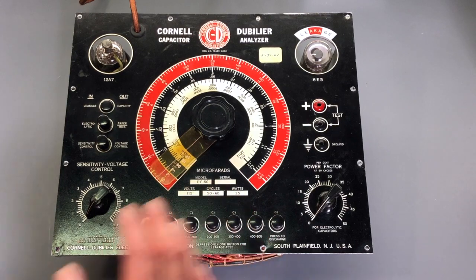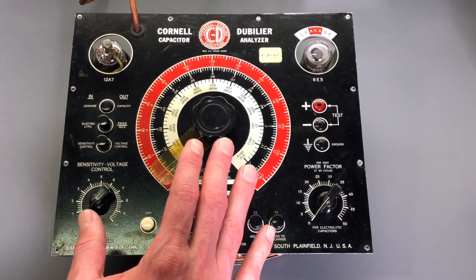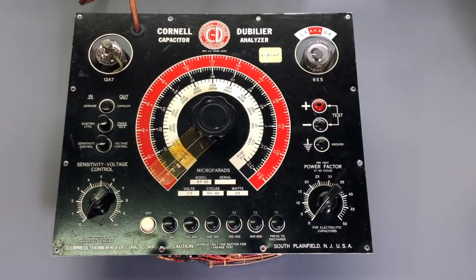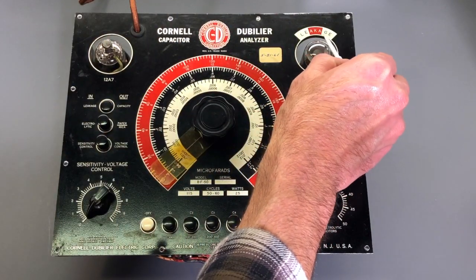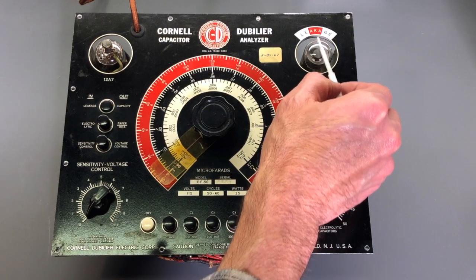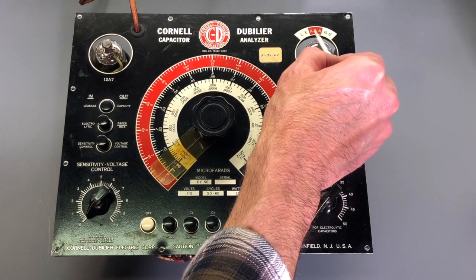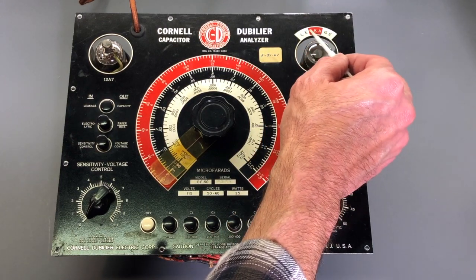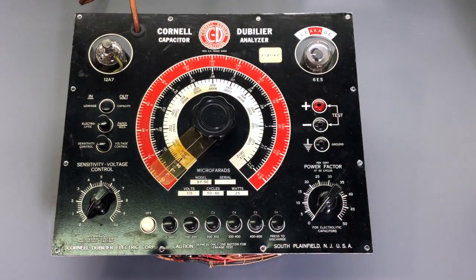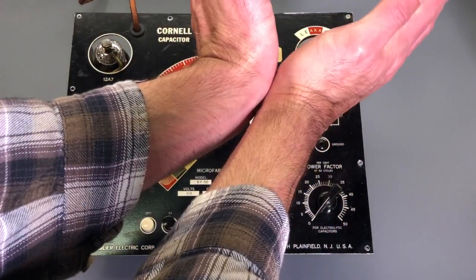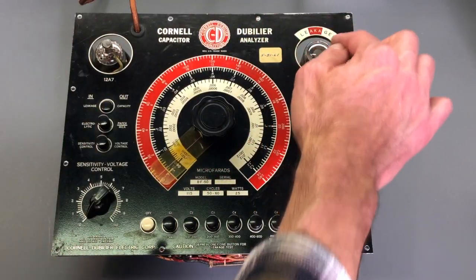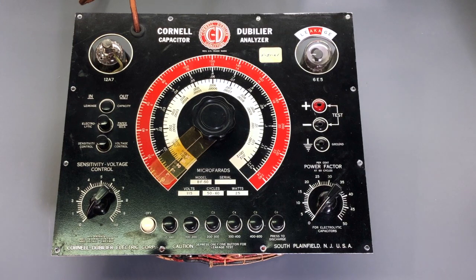So if the capacitor under test is very leaky, the eye will close together, and that's what this red area is indicating. So if the wedge shape is equal or smaller than this wedge shape right here with the red, then that would indicate a problem. And what you're looking for during the leakage test is really a wide open wedge shape in that green color, and that'll be very obvious once it's powered up.